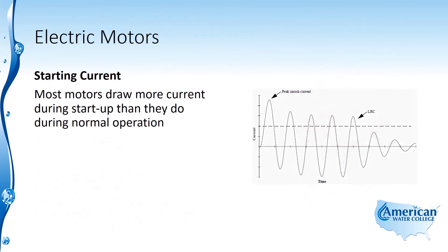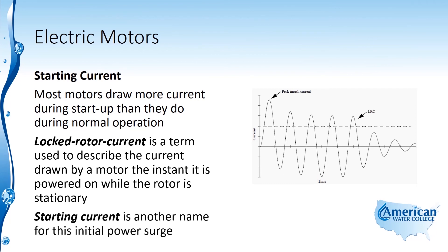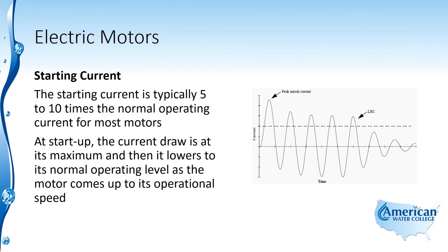Most motors draw more current during startup than during normal operation. Locked rotor current is a term used to describe the current drawn by a motor the instant it is powered on while the rotor is stationary. Starting current is another name for this initial power surge. The starting current is typically five to ten times the normal operating current for most motors. At startup, the current draws at its maximum and then lowers to its normal operating level as the motor comes up to its operational speed.